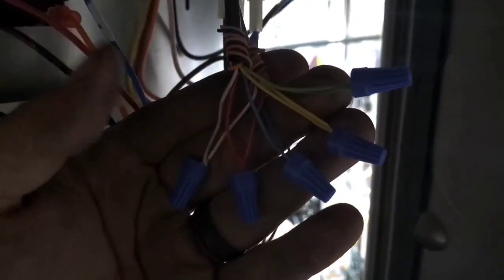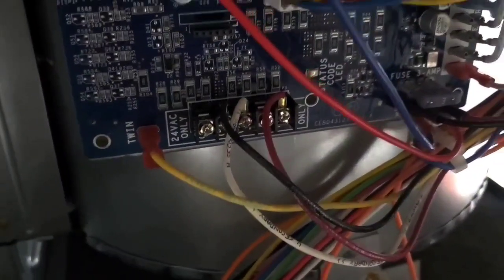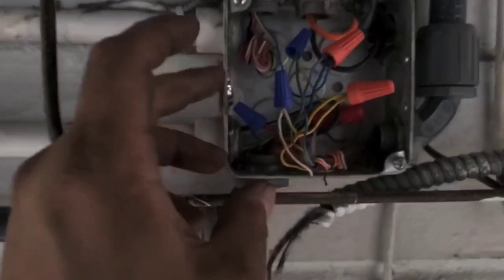Now, over here in the slave unit is a splice. The 2 thermostat cables go together. And now if you're over here working on the slave unit, you can jump out the terminal strip because, you know, you can't do anything with that. Here's the thermostat wiring now.